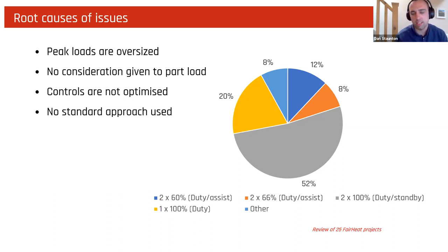We had a quick look at the last couple of years' worth of designs that have used plate heat exchangers, from other consultants and clients. Around 50% used a duty standby approach, 20% used the duty single plate approach, another 20% used the duty assist approach, and 10% were something else. There's no clear standard being used, and that's preventing lessons learned being taken forward into the commissioning and specification of plate heat exchangers and control valves. And that was the purpose of Lucy's project.